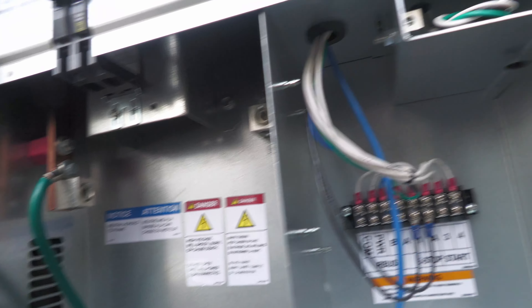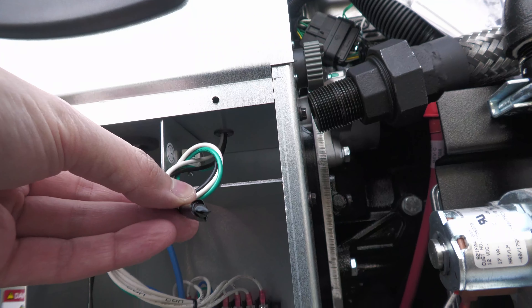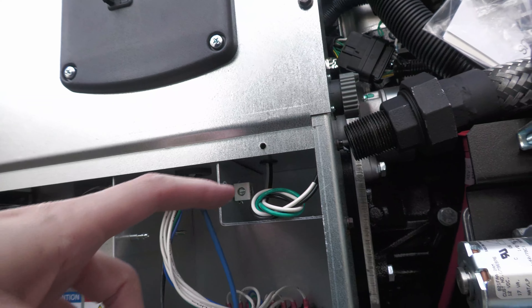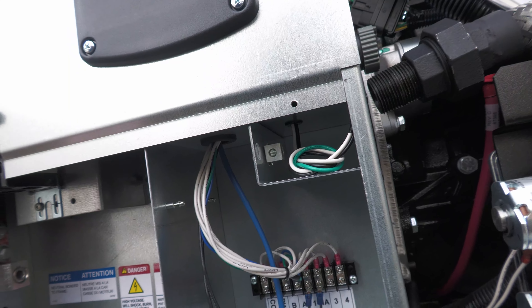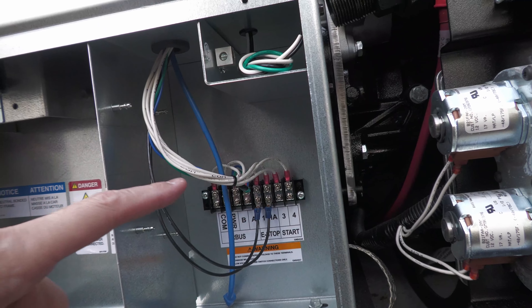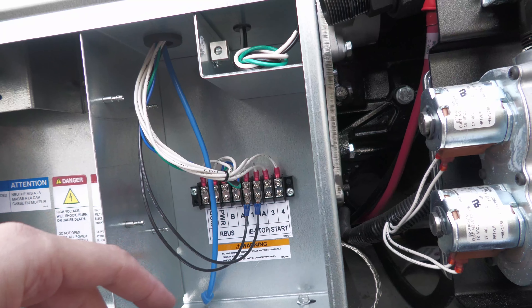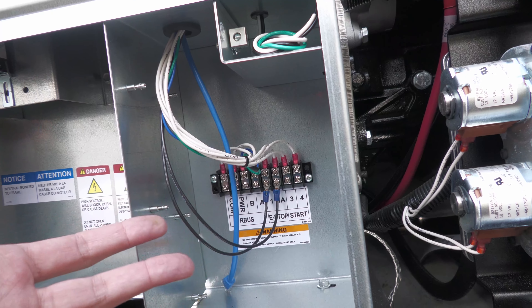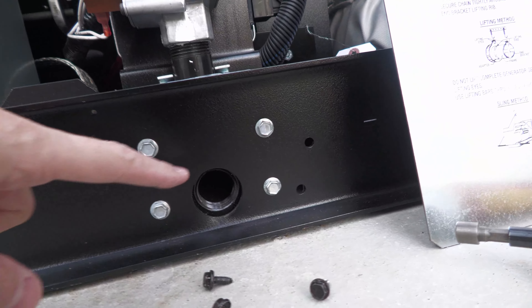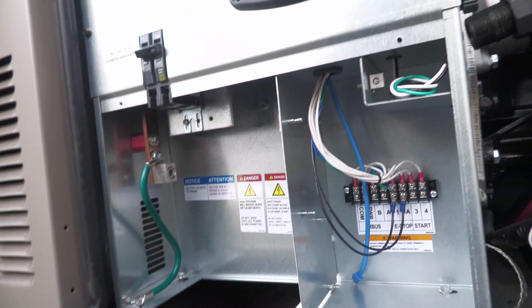The only other things going on here: these wires are for power in. This generator doesn't just supply power going back to the house — it also needs a feed of 120 volts AC that runs the battery charger. So when the generator is off, it can keep topping up that battery. Over here are the terminals for the communication protocol. They have something called R-bus, so there's low voltage wiring that goes from here back into the house and connects to the transfer switch.